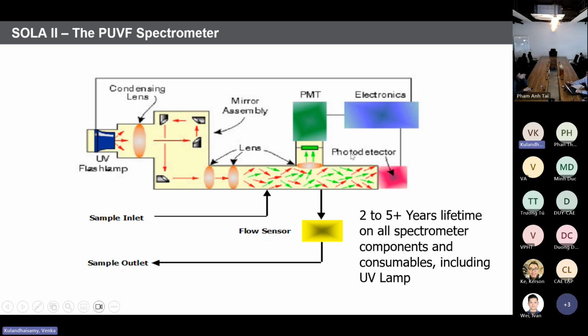So normally our PMT bench lifetime is 2 to 5 years. All spectrometer components and consumables, including the UV lamp, have a 5 year lifetime. But for the UV lamp, based on the concentration you are going to measure, the life can be shorter, maybe 2 years. Sometimes it can go up to 5 years. If you are going to measure very low ppm, the UV lamp life will be longer. If you are going to measure high ppm, then the UV lamp life may be shorter.